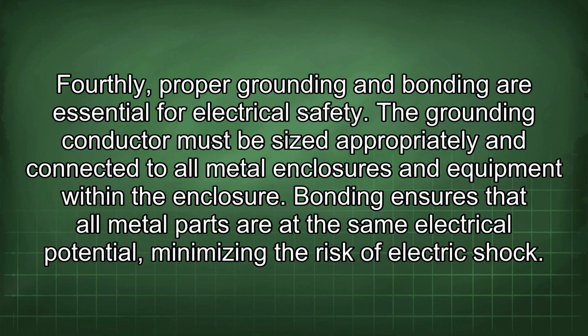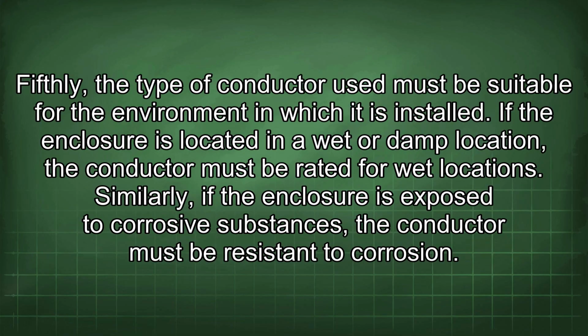Fourthly, proper grounding and bonding are essential for electrical safety. The grounding conductor must be sized appropriately and connected to all metal enclosures and equipment within the enclosure. Bonding ensures that all metal parts are at the same electrical potential, minimizing the risk of electric shock. Fifthly, the type of conductor used must be suitable for the environment in which it is installed. If the enclosure is located in a wet or damp location, the conductor must be rated for wet locations. Similarly, if the enclosure is exposed to corrosive substances, the conductor must be resistant to corrosion.